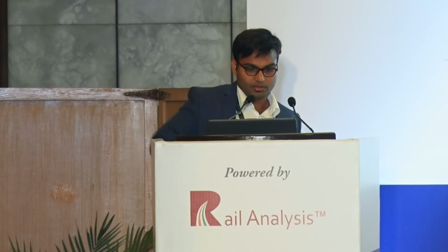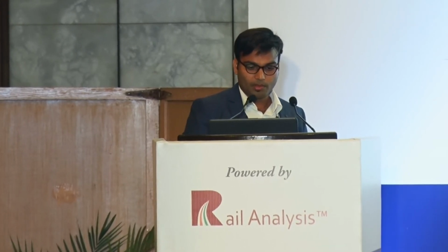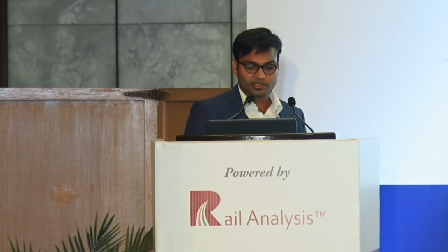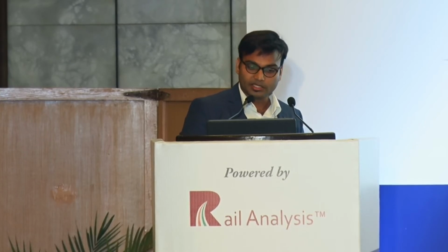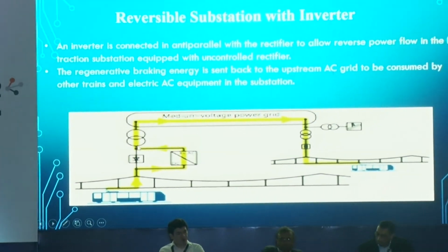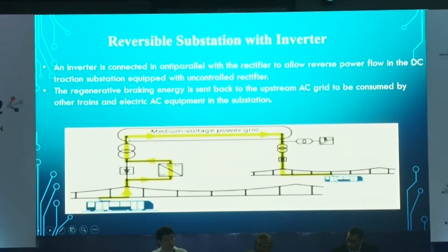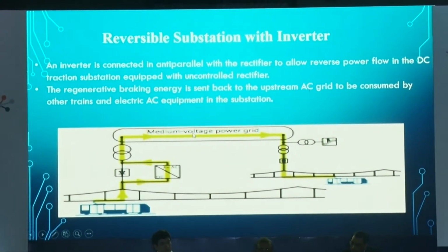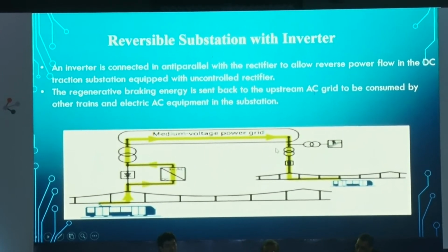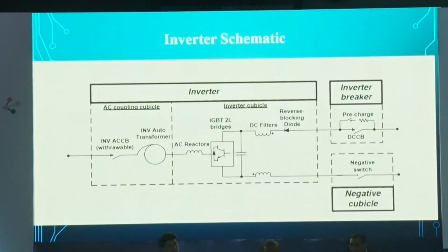That means the power will flow when the train is braking. The regenerative power will flow from the DC traction system, and here it will be again converted through this inverter into AC, and through some mechanism, maybe through transformer or auto transformer, this will be fed to the secondary of the main transformer, and it will be fed to the medium voltage grid. When the energy is fed back to the medium voltage grid, it can be utilized anywhere in the grid. Maybe in the auxiliary system, maybe in other trains which are far away from the generating train. So this is the beauty of this reversible substation.